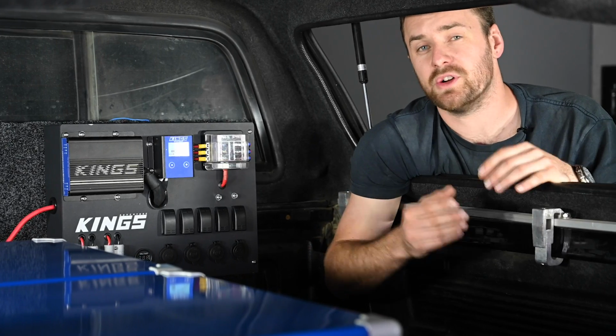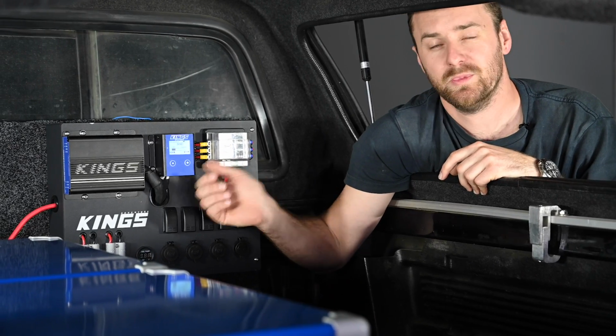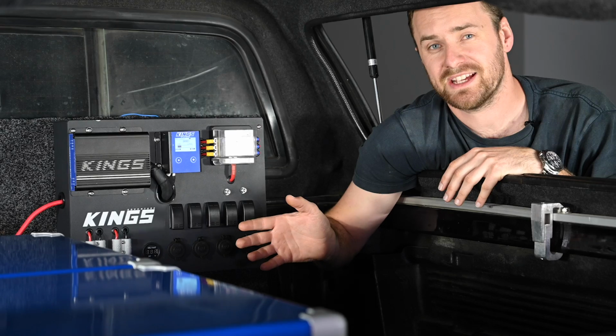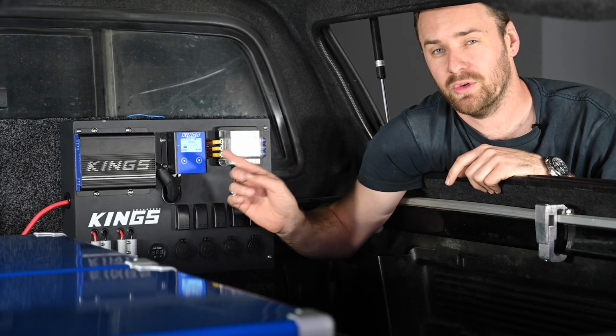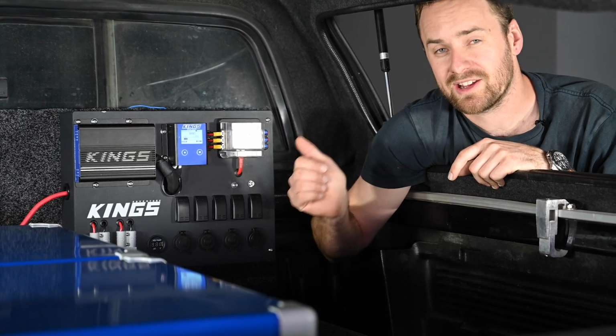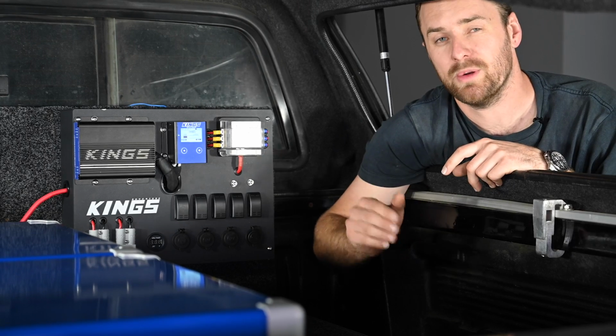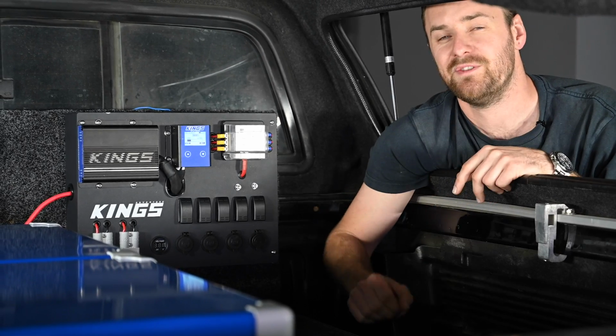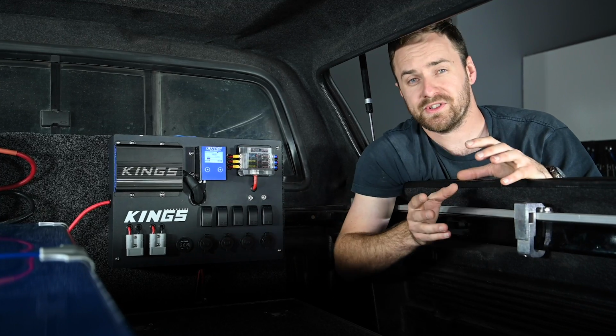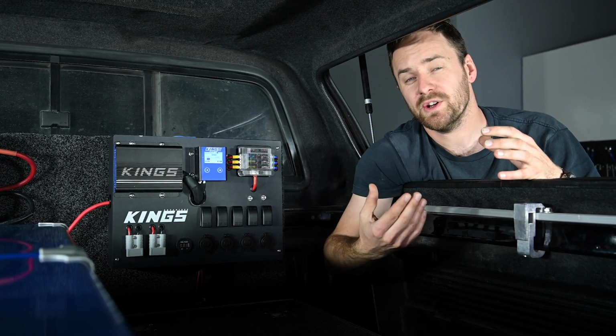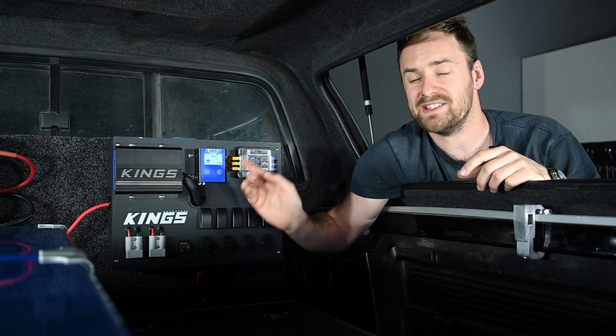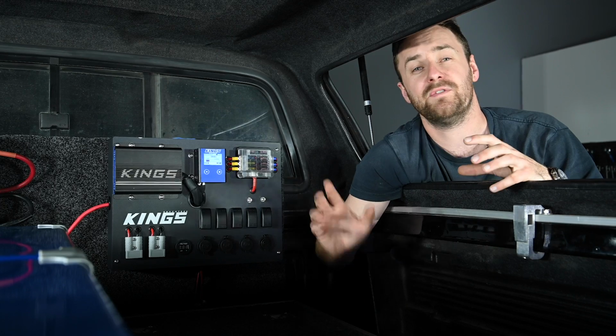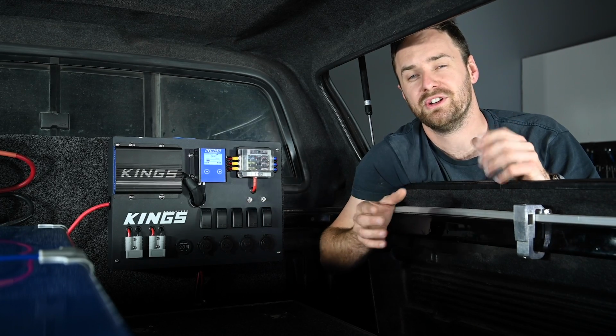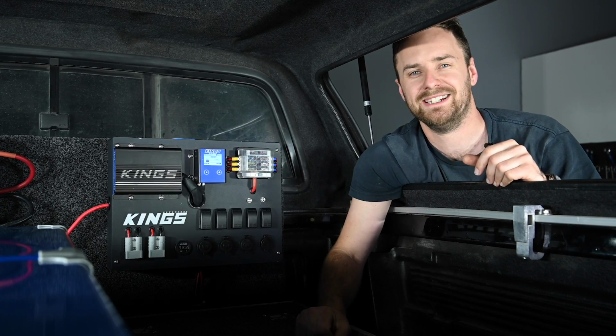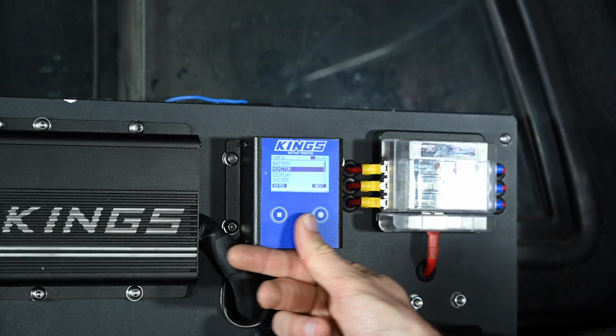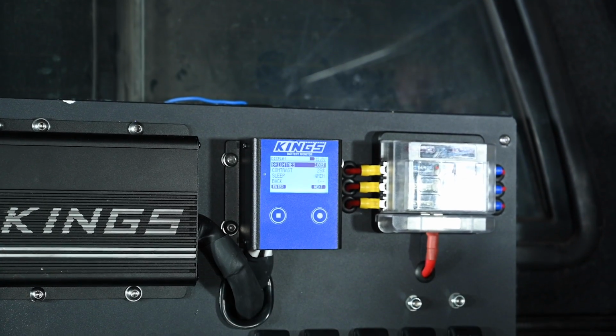Now with an under voltage or over voltage situation, this unit will automatically reconnect after a 30-second delay, assuming you've got it set on the auto mode. But if you get an overcurrent situation, it doesn't have an automatic reconnect. That's a built-in safety feature. So if your system has a short circuit somewhere, or you've got a device with an internal fault that's drawing excess power, this isn't just going to keep turning on and off again. If there is a problem, you'll be able to find it, troubleshoot it, fix it, and then turn this back on manually. Hitting back takes us back to the main menu again, where the next option is display.